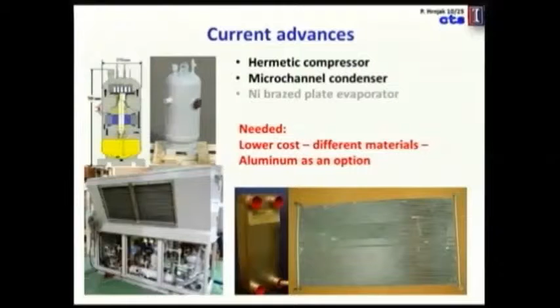We have been working on this since '96. This is the first prototype of an air-cooled chiller with 18 grams per kilowatt at the 50 kilowatt level. I'm very glad that after a few years we were asked to help, and this is one of the chillers—an air-cooled ammonia chiller, 35 kilowatts with a hermetic compressor. I'm also aware that in Italy there is another recent low-charge ammonia system.